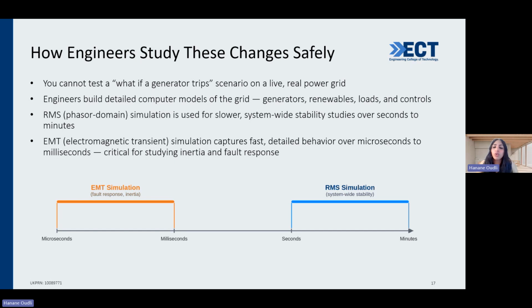The right model depends on the question. If I'm asking how a larger system responds over several seconds, RMS may be enough. But if I'm asking how an inverter interacts with the network right after a disturbance, I may need EMT. That's why electromagnetic transient simulation is not optional anymore - it's very essential and critical to assess and simulate our grid before it goes live.